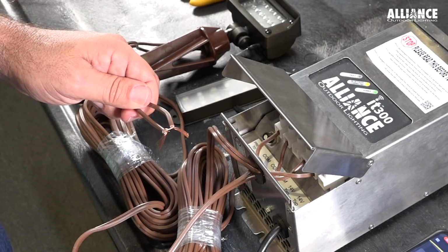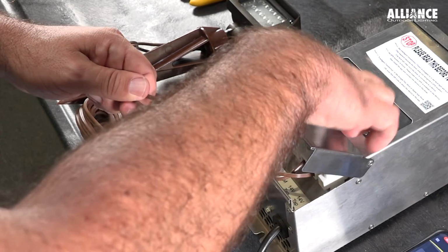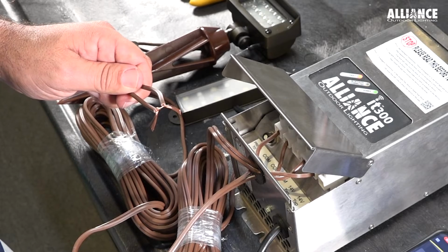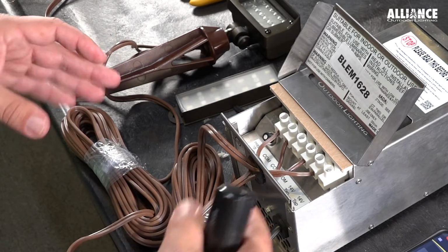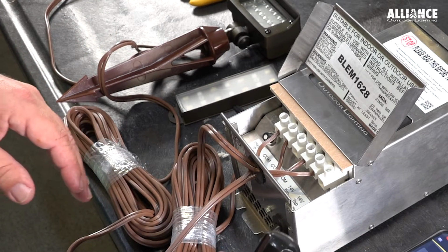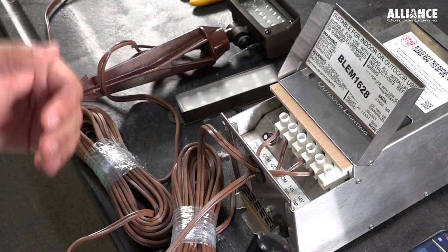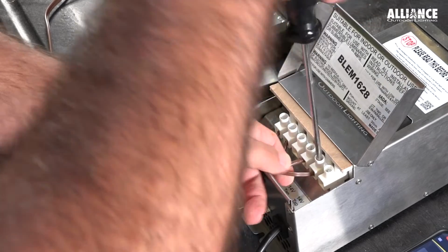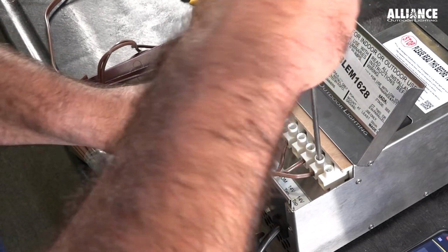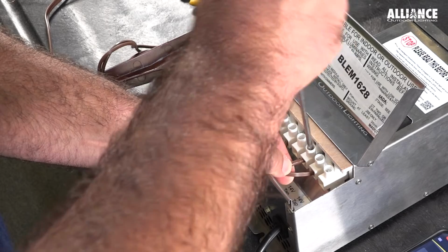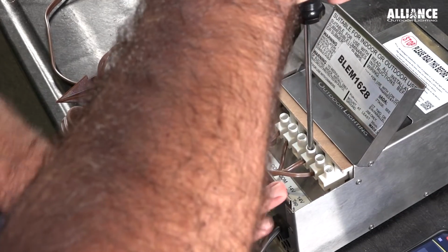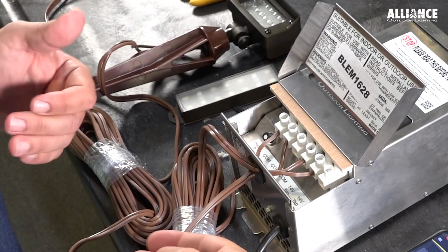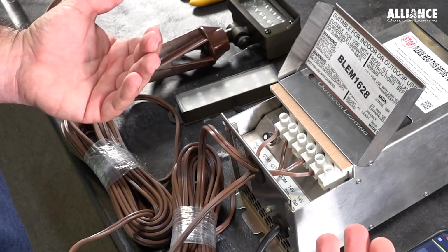So when you turn the transformer on, if it immediately faults, more than likely you have a short in the field someplace. The easiest way to determine which line out of the transformer the fault is on is to remove these wires and then put them back in one at a time. So you can remove both sides or one side of the wire. I typically leave the commons in and remove the hot or the tap side, but it doesn't matter which way you do it. You can also remove all of the wires and add them back in one at a time.